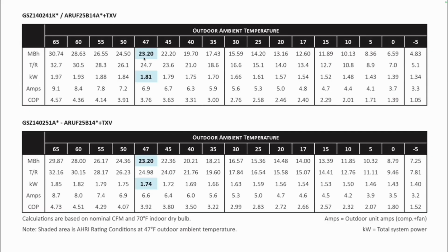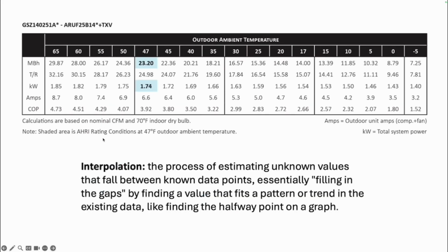So this is actually Goodman's heating chart, and I'm going to blow this up a little bit so it's easier to see. Now, this is a 2-ton Goodman. This is a GSZ 14, which is a 14 SEER Goodman. The 25 is a 2-ton. They have a 24 and a 25. The 25 is made for the longer line set, so it's more of a long line that's used in multifamilies. And notice here that it says the calculations are based on nominal CFM and 70-degree indoor dry bulb.